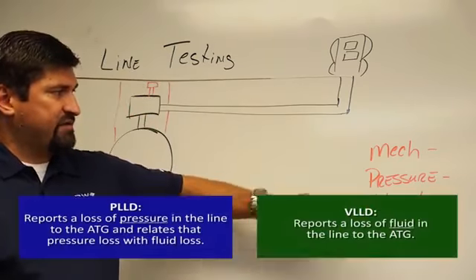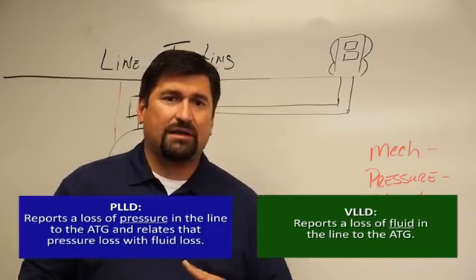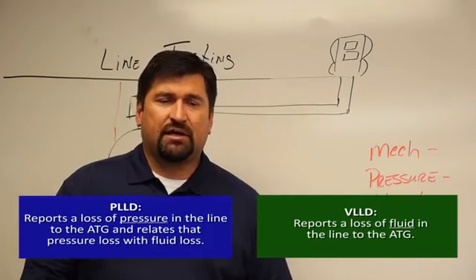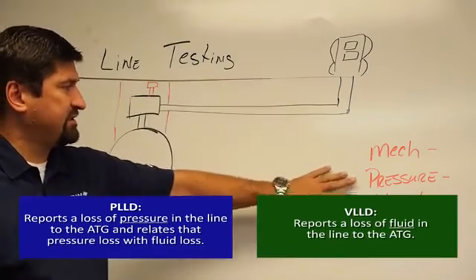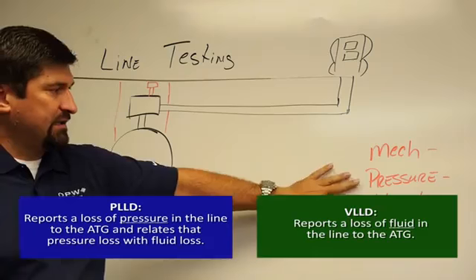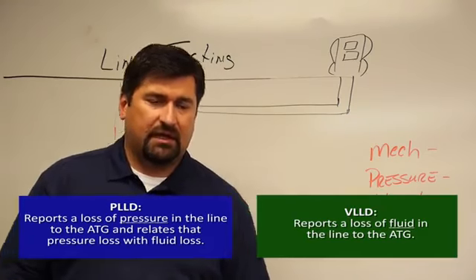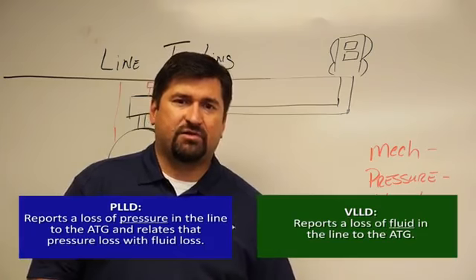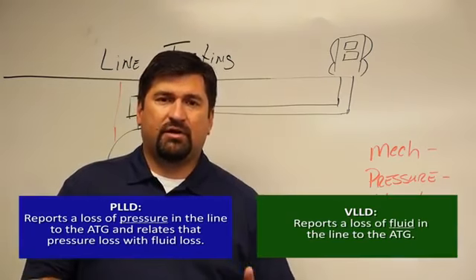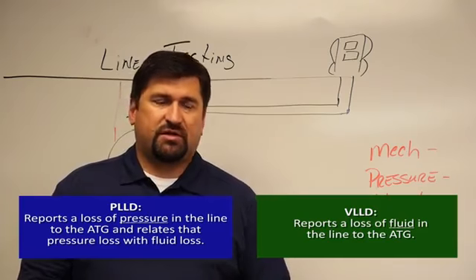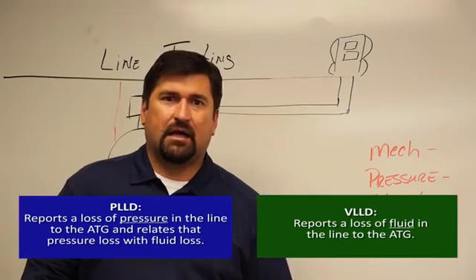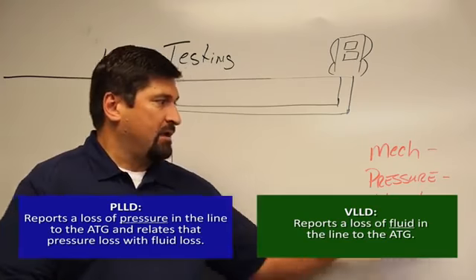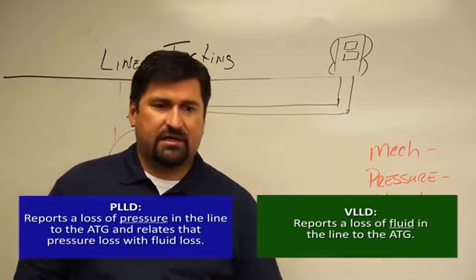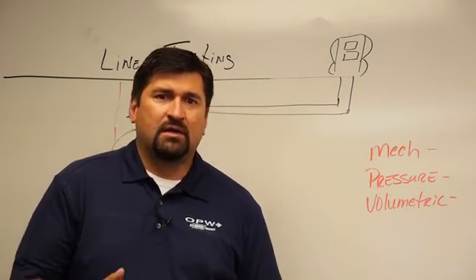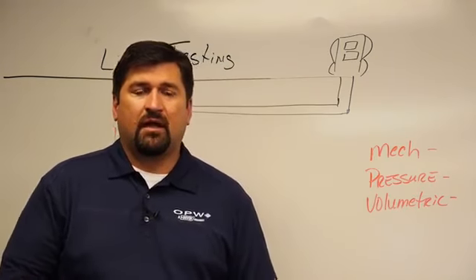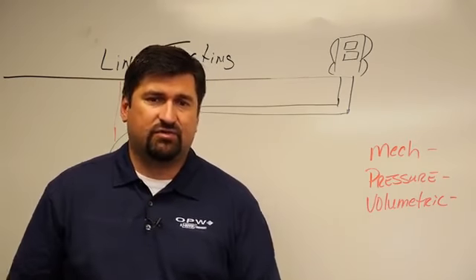Well, the other two that we have are pressure and volumetric. Pressure and volumetric are electronic line leak detectors. These are looking for leaks within the line, and they're actually talking back to the console. Now, when you look at the difference between a pressurized line leak or a volumetric line leak, pressure is looking at the decay of pressure over time, or they're trying to correlate pressure loss to a volume loss. The restrictions that you run into are line length, line diameter, and pipe type. The other one is a volumetric test. Volumetric is where you're looking with a very accurate flow meter to determine how much product is leaving the line, whether it be through a third-party test or through a test through the ATG.